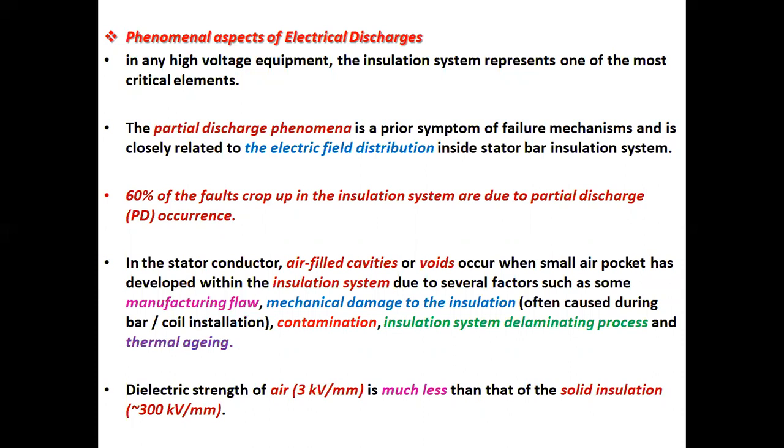In the stator conductor, air-filled cavities or voids occur when a small air pocket has developed within the insulation system due to several factors such as some manufacturing flaw, mechanical damage to the insulation often caused during bar or coil installation, contamination, insulation system delaminating process, and thermal aging. The dielectric strength of air, 3 kV per millimeter, is much less than that of the solid insulation, that is 300 kV per millimeter.